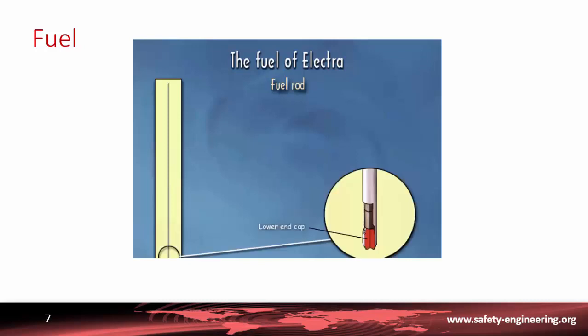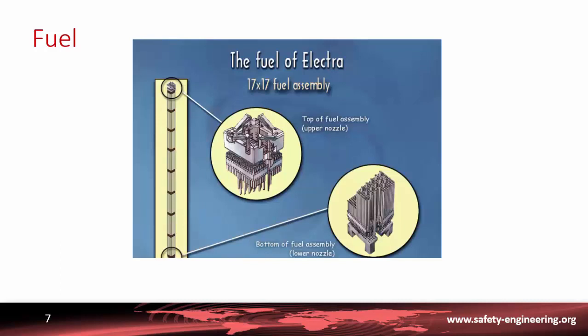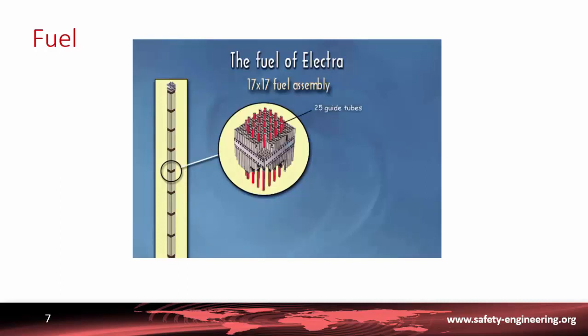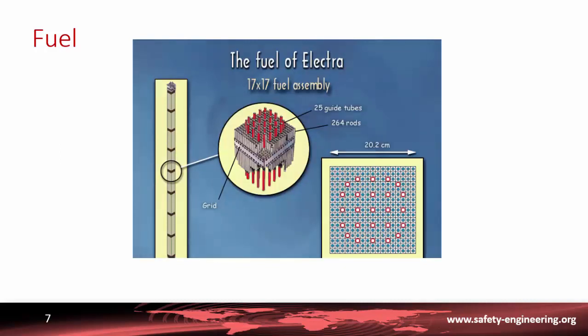End caps are welded to the ends of the rods. At the top there is an empty space, referred to as a plenum, that contains a spring to receive the gases released by the fuel while it is in the reactor. These rods are combined in sets to form fuel assemblies. The top of the fuel assembly, or upper nozzle, is designed to facilitate handling. The bottom, or lower nozzle, ensures accurate positioning on the support plate in the reactor vessel. The fuel assembly is rigidified by 25 guide tubes linking the two end fittings. Grids attached to the guide tubes receive the 264 fuel rods. These grids are square, each side approximately 20 centimeters long with 17 rod positions. They maintain the rods at regular spacing, prevent them from vibrating, and facilitate water flow.